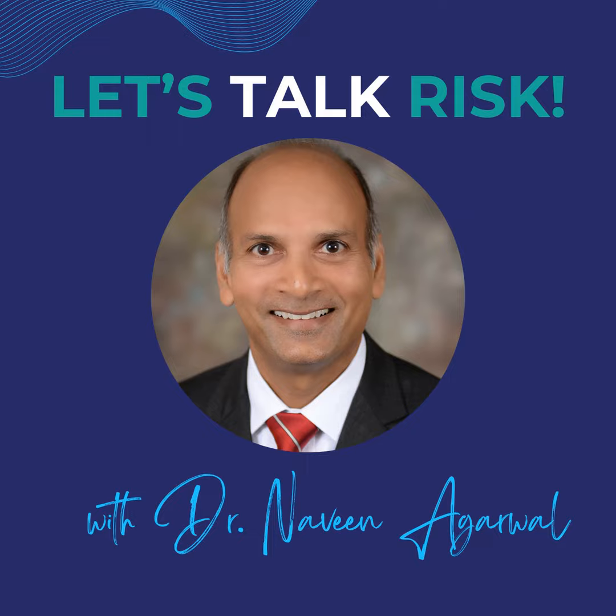Good morning. I agree with all the points with development and risk, more especially on standards and developing your risk analyses. With that, one thing to just add is with your usability testing, formative analysis will greatly add to that risk assessment. That's something to consider early in the feasibility phase, and you can get those pre-inputs to help develop that risk package.